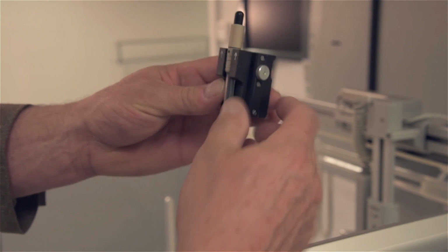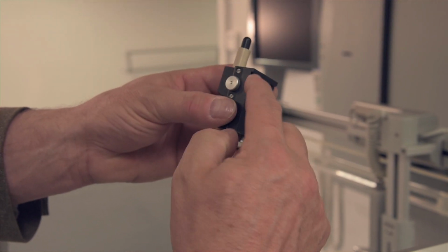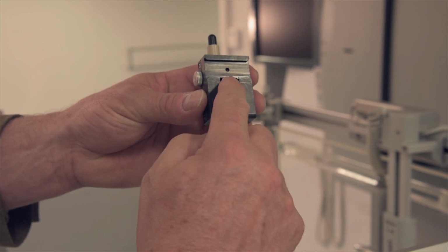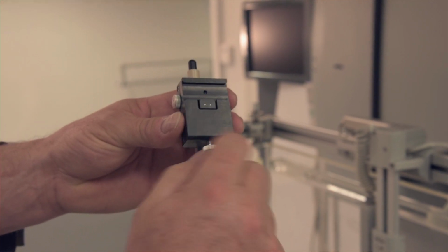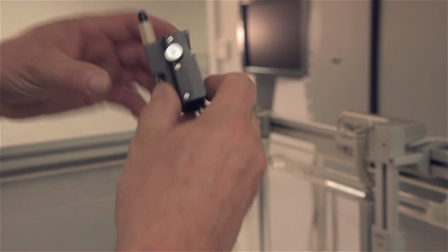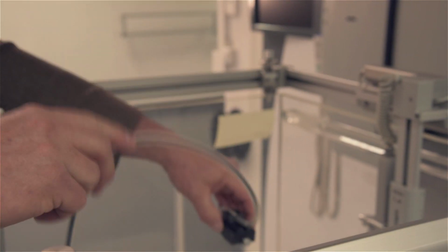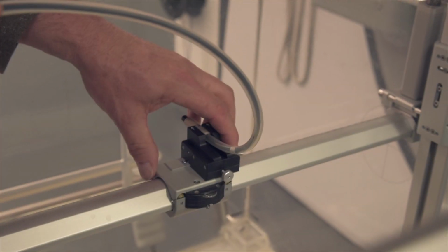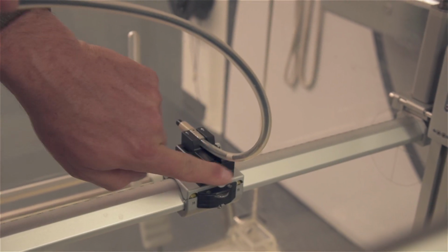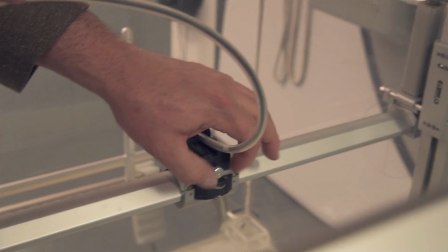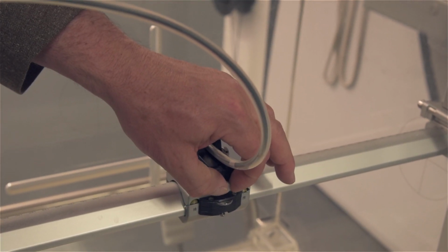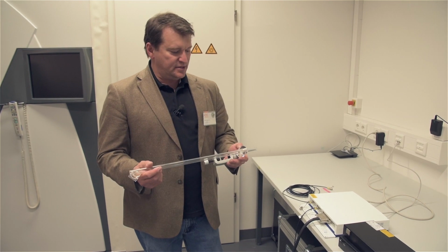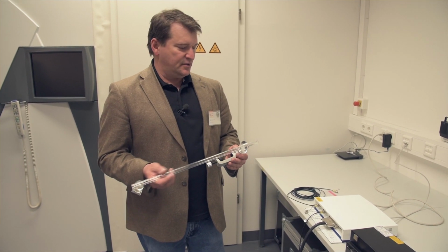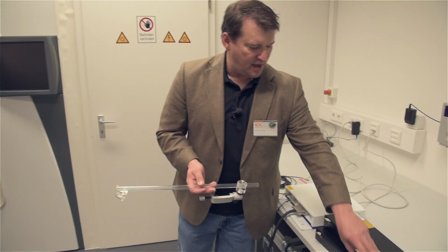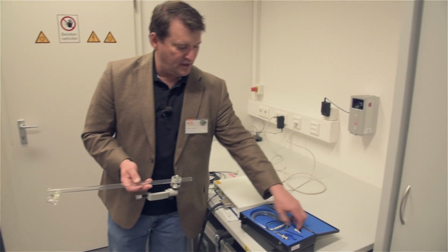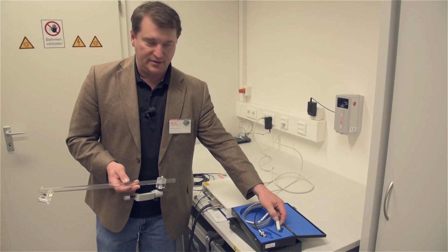Snug it up with this knob, and you'll notice this is a dovetail fit underneath, and it's adjustable by this screw, which moves that foot back and forth. You want to back it all the way out, and then you want to place this on that holder. Once it's in place, you want to snug it with this knob at the back, just like so. So this is our reference probe holder. So you can do this a couple of different ways. I'm going to go ahead and put the detector on here and then place the detector and holder both onto the tank after the fact.